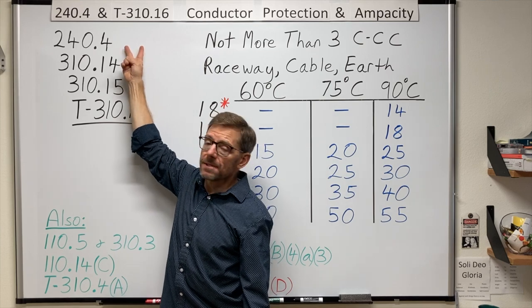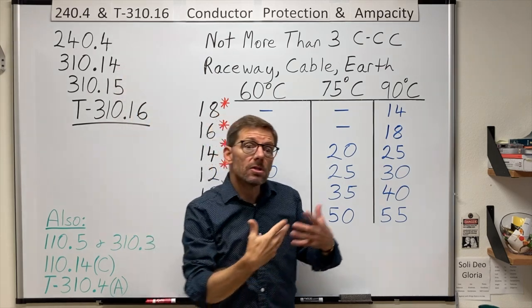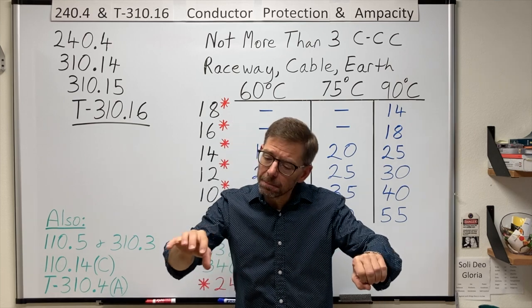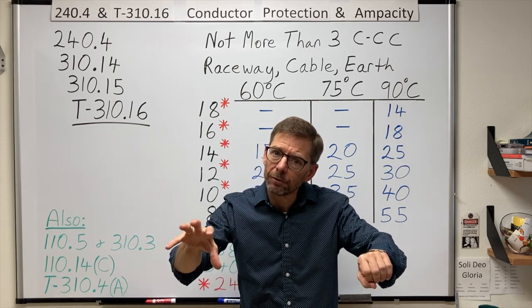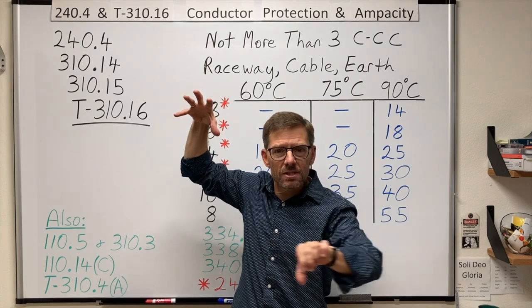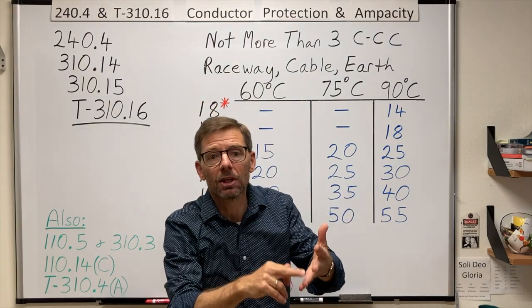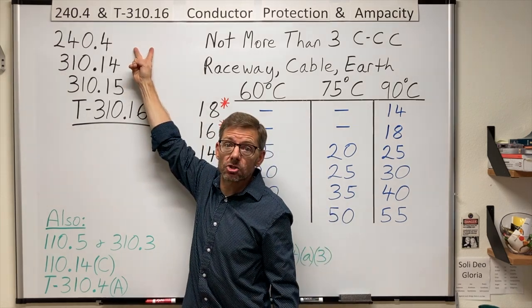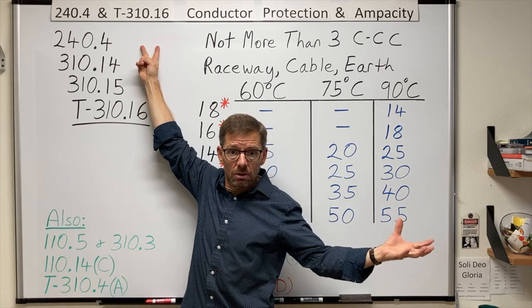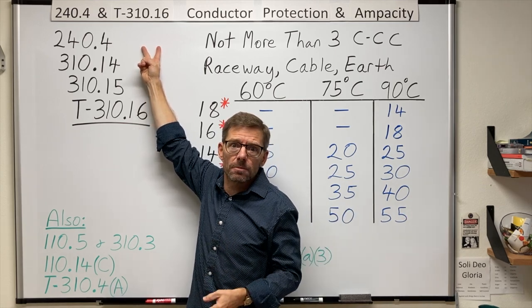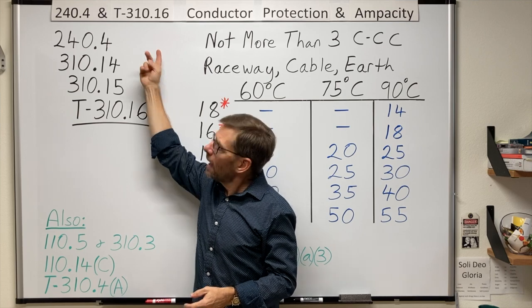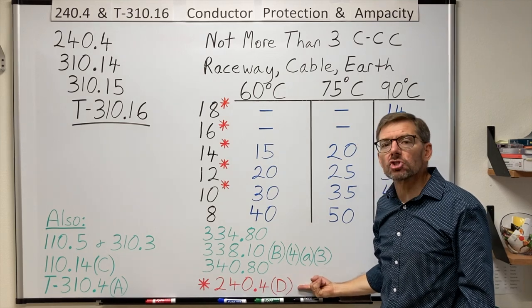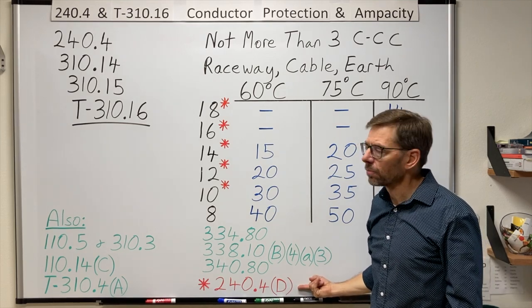These subsections here allow certain permissions or have restrictions. A permission might look like a conductor that appears to be protected by an overcurrent device that is too big for its size. Think of motors, tap conductors, welders, other things. And they're specified in these subsections. It tells you where to go in the code to make safe installations in those circumstances. And a restriction we're going to bump into shortly is in 240.4D for small conductors.